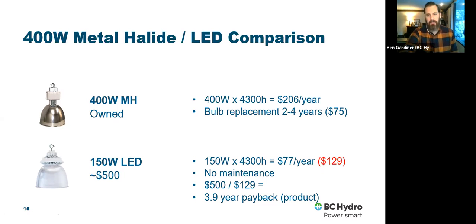If it runs for the exact same time, in 2020 dollars it'll cost you $77 a year to run that one light. So you're already saving $129 a year just off that, with no maintenance to it. $500 divided by the savings of $129 equals a 3.9 year payback - a little less than 4 years. So if you installed that light today, just on energy savings alone, assuming your business continues operating in a linear fashion, it'll pay itself off in less than 4 years. After that, your bill is still reduced by $129 a year - that's money in your pocket.